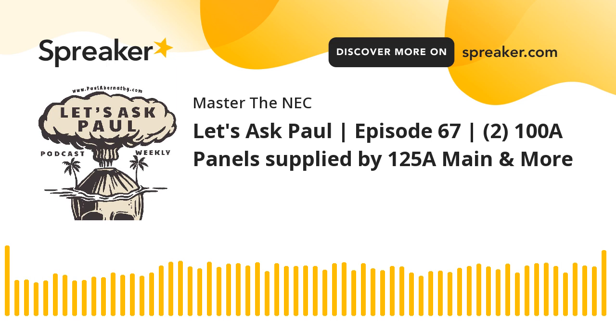At any time you don't understand the difference between a type 1, a type 2, type 3 type of surge protective devices, I encourage you to go look at Article 242. You're not going to see that, folks, in your 2017. You're going to end up having to go and look at the 280 and 285 when you're dealing with surge protective devices, and then lightning arresters if you're dealing with that application. But now it's all in 242 of the 2020. Okay, so again, my lesson is assuming you're using the 2020, so we're going to go with that.